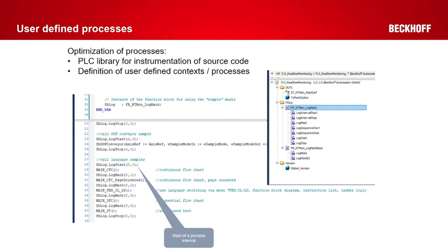Everything which has to do with analysis or something like this is completely done offline in the real-time monitor, to get this interface as fast as possible. Furthermore, the main difference between TwinCAT Scope and the real-time monitor is that in the TwinCAT Scope you can grab information only by cycle time, and in the real-time monitor you have an interface which says now, and then we provide a timestamp with the three numbers I already mentioned.